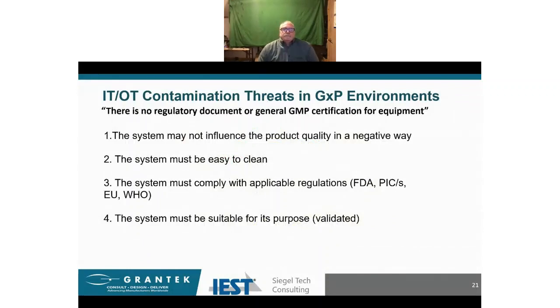So when we talk about equipment and things, there is no regulatory document or general GMP certification for equipment. There's typically 4 ways we approach systems. When I say systems, that could be a portable device, an instrument. It could be something installed. Could be the manufacturing equipment itself. But important to understand, the system may not influence the product quality in any negative way. It must be easy to clean, and those are the 2 most important caveats that we're talking about. The system also must comply with applicable regulations, FDA, PICS, EU, WHO, EMEA, IEEE, and so forth. And the system must be suitable for the purpose. It must be validated. And there's an entire talk you can have about validation, but it has to be suitable for what it is there to do. Next slide, please.